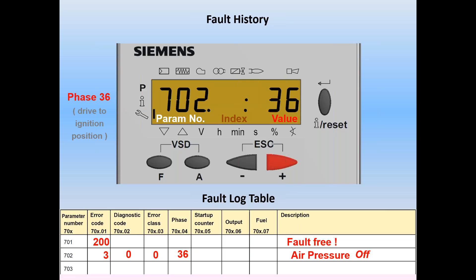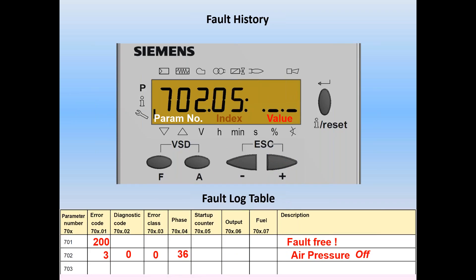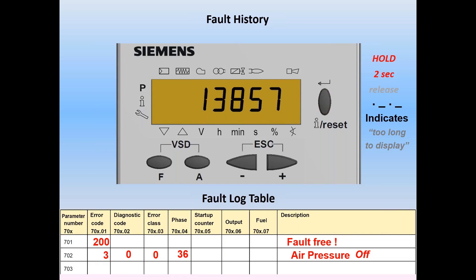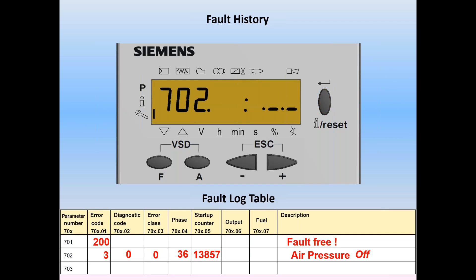We do a plus and move to index 05, which shows a value of dot-dash-dot-dash. This indicates the value is too big to display in those four spaces. Hold the enter button for two seconds and let go, and the screen transfers over to the full value — in this case 13,857. That's the cycle count on this burner when this error occurred. We put 13,857 in the chart. There's no time and date stamp, but the cycle counter tells us how frequently this problem is occurring. Push enter again to return to index 05.